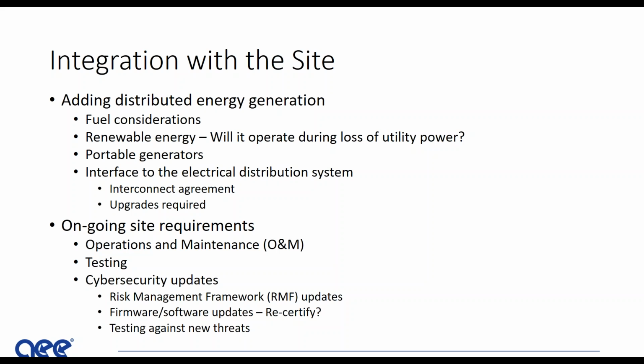Renewable energy - will it operate during loss of utility power? It'll operate, but without a reference voltage and frequency, you're not going to do much with it. You need to make sure you have that available. Usually what we're doing now is using a battery energy storage system on the inverter - we allow that to power our renewables on site.